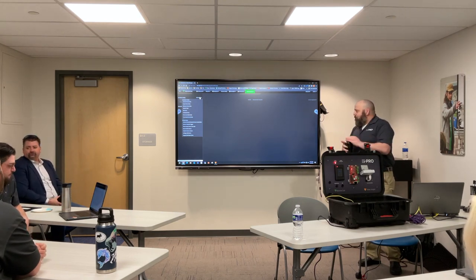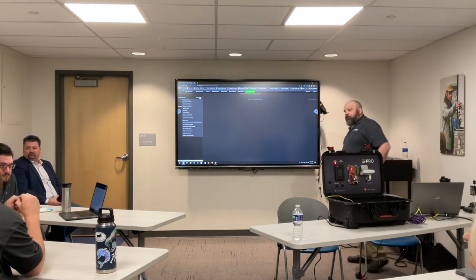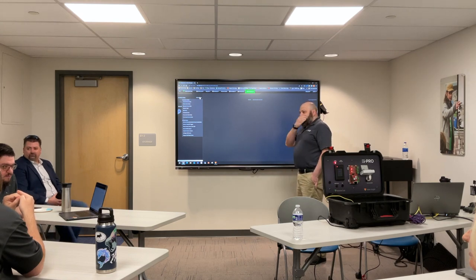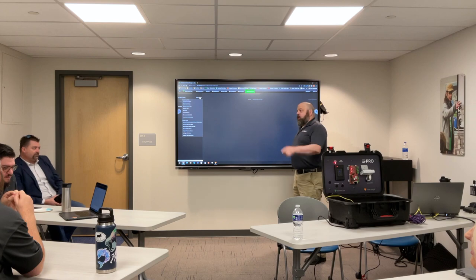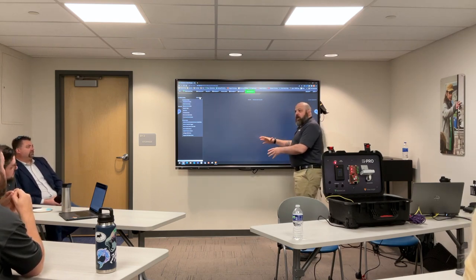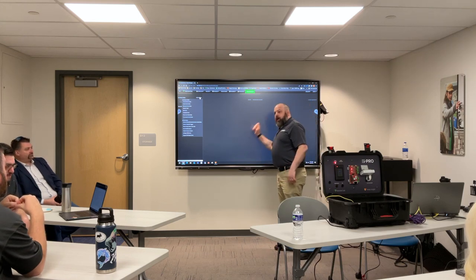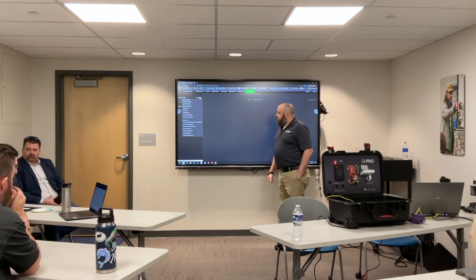How does that work if we have a snow day and want the doors in the building to stay locked, but have custodial there still plowing and shoveling sidewalks, and if they need to run in and use the restroom? You would apply it to specific people. Okay. So for custodial staff, the door would just stay in the card or pin state. If an administrator comes in, maybe you say principals, assistant principals, if they swipe in on any exterior reader, go ahead and unlock it. That's selectable. Okay.